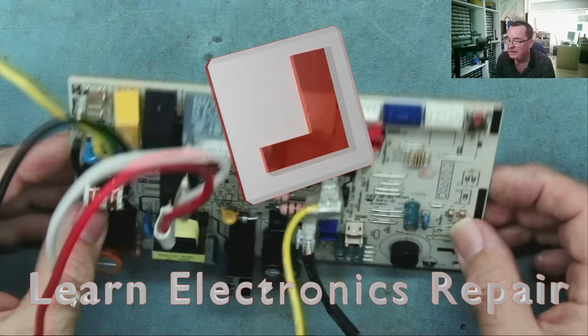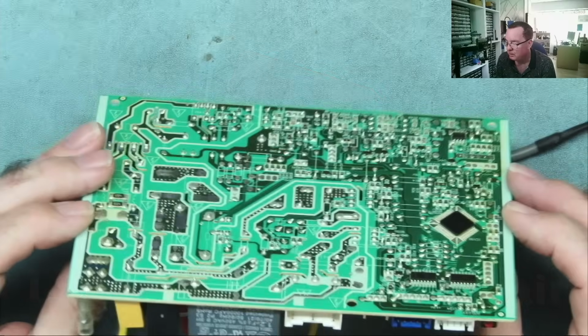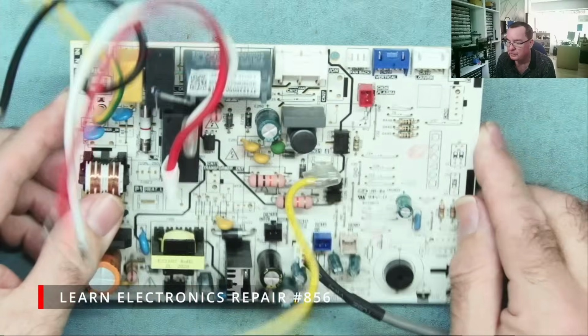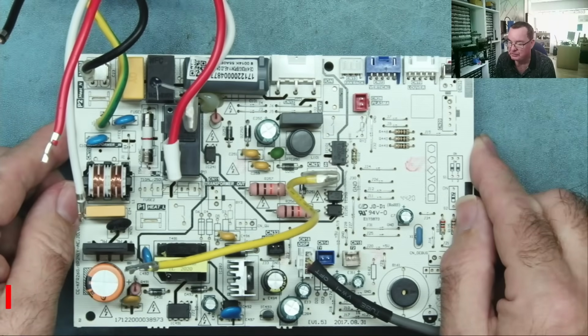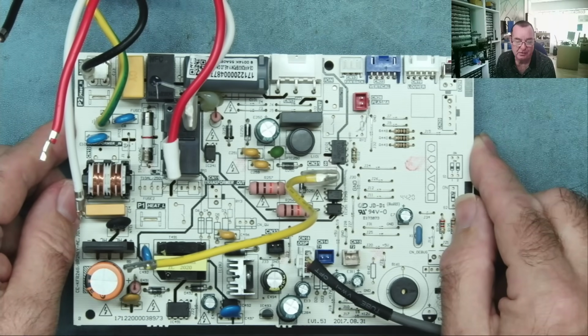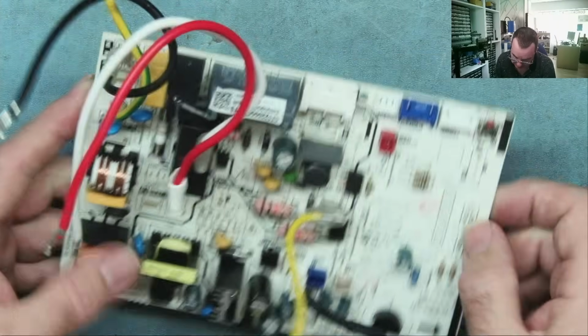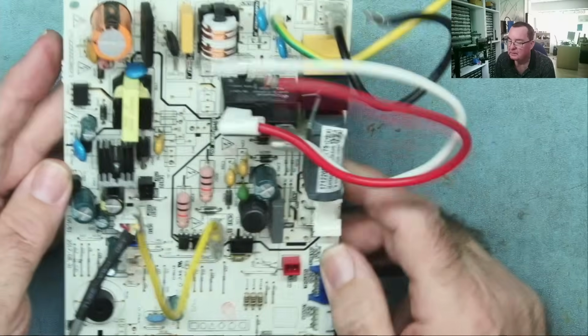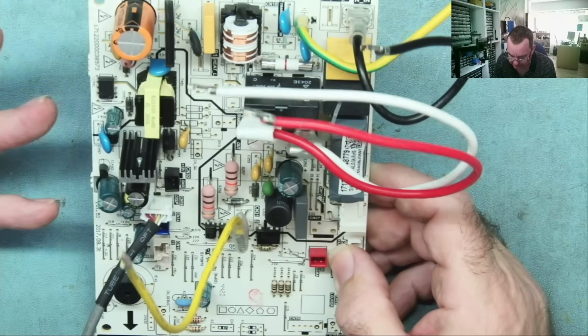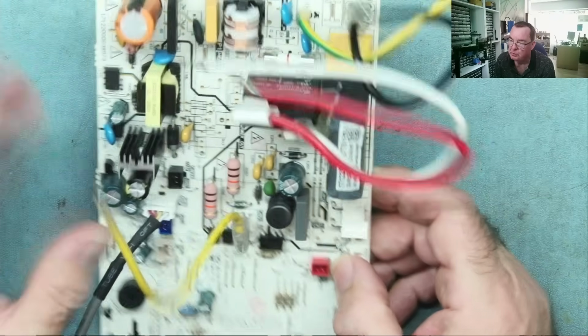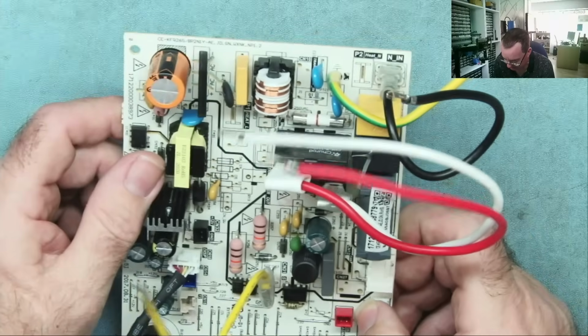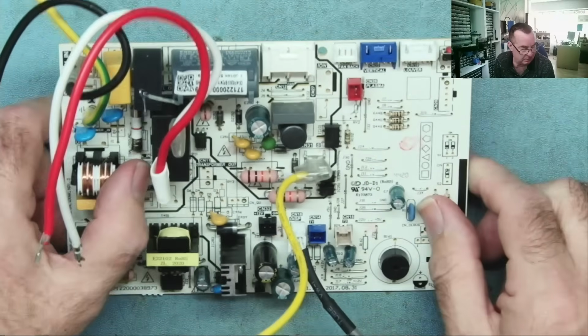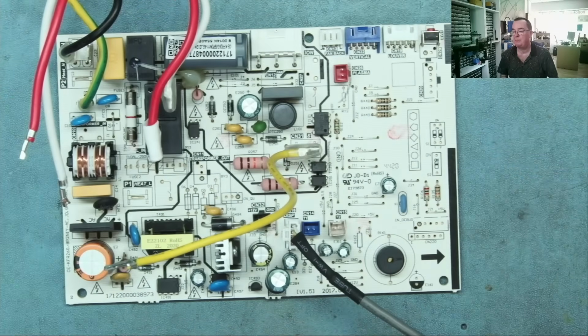I have a board here from the indoor unit of a split air conditioner, or HVAC. This is the PCB, or one of the two PCBs that goes on the indoor unit. The other one's like a little display board. It has an error code on which suggests there's a communication error between the indoor and the outdoor unit.